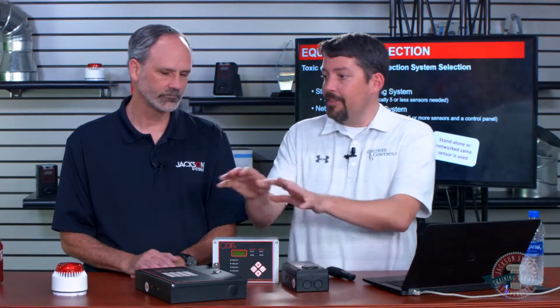We're actually putting a communication wire between the sensors and the panel itself. We are making sure that we are getting alarms at both the sensor and the panel level. So there's a lot more, not a lot more to it, but just a little bit more to it. We're actually programming the panel and the sensors to do specific things. So there's a lot more to it in terms of that.